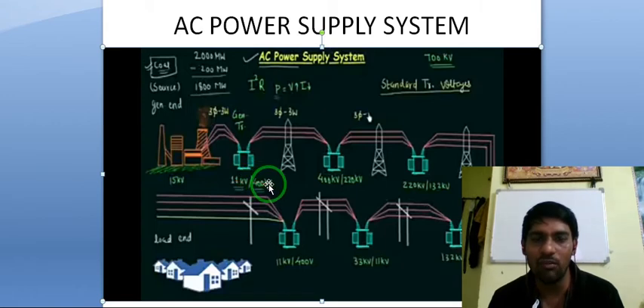We step up the voltage level from 11 kV to 400 kV in order to reduce the current, because power P equals V into I. So when the voltage is very high, the current is reduced. When the current is reduced, the I square R loss is reduced. That is the reason why we step up the voltage level from 11 kV to 400 kV. So this transformer is called a generating transformer. The main function of the generating transformer is to step up the voltage level.